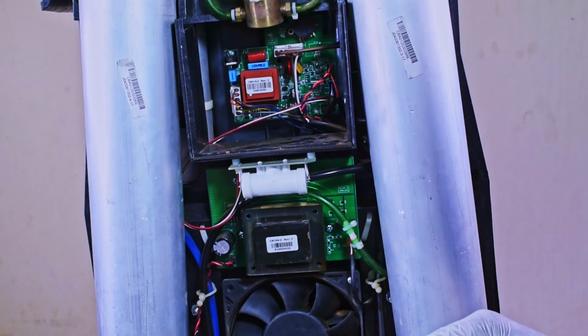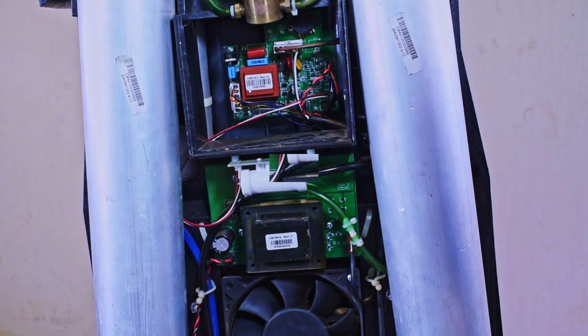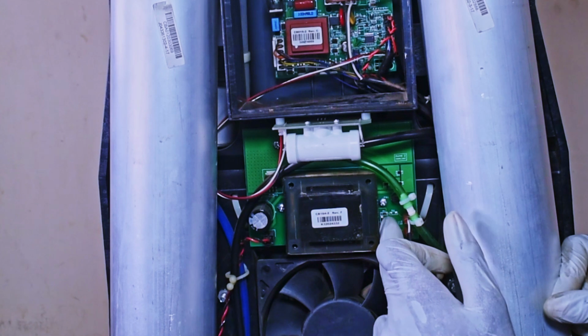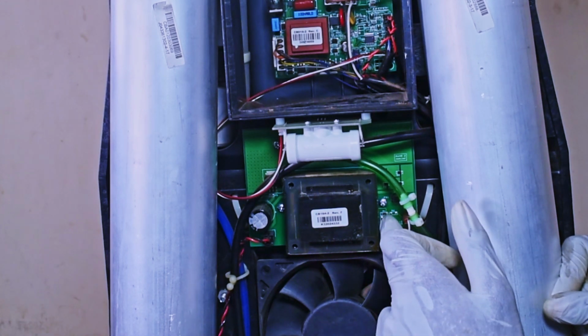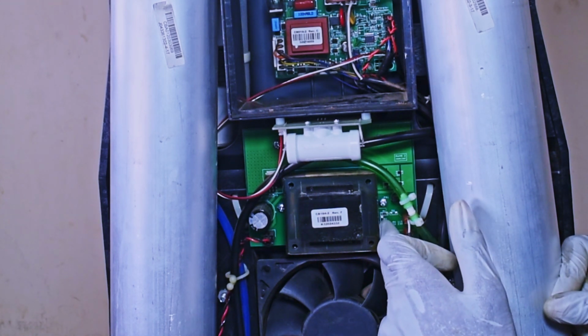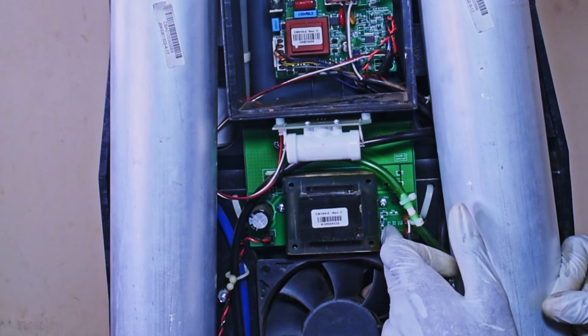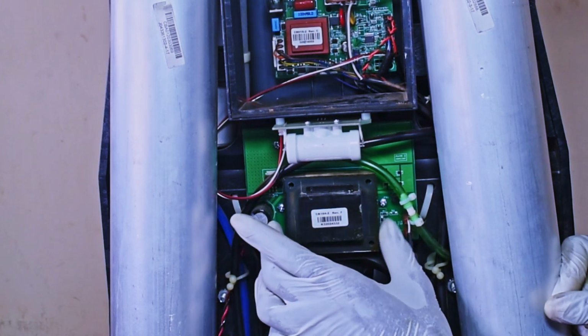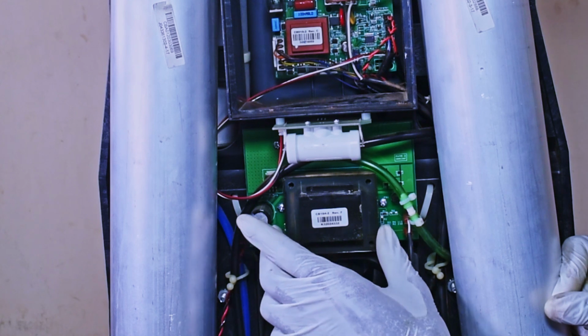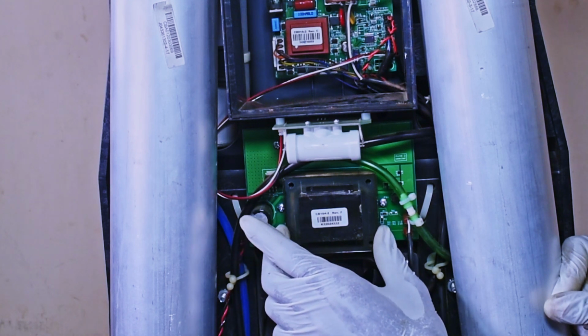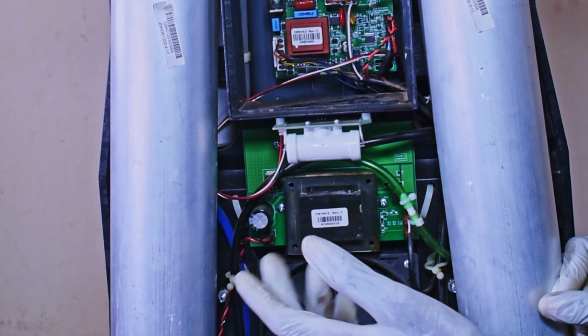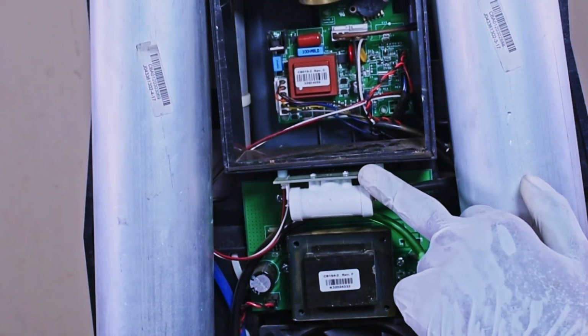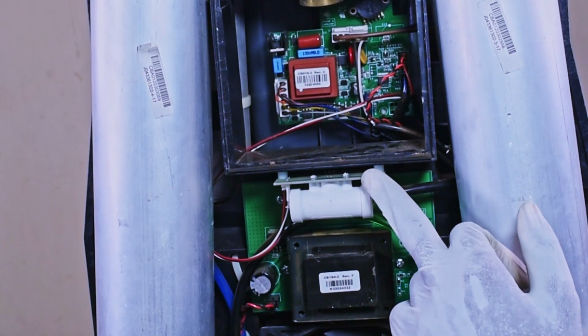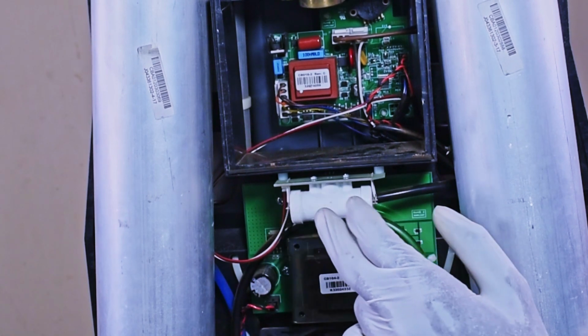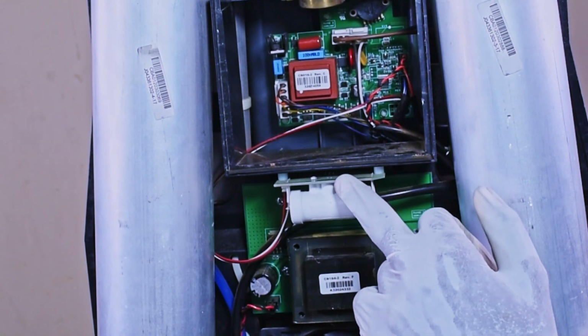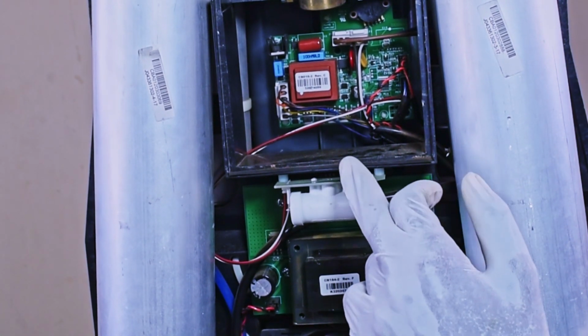The oxygen concentrator has 3 printed circuit boards. On the bottom, we have the fan control board. This board controls the operation of the fan and provides power to the fan. It has a step-down transformer which is used to lower down the voltage suitable for fan operation. And over here we have the oxygen monitor circuit board. So there is an oxygen monitor on the board which monitors the level of oxygen concentration produced by the unit.